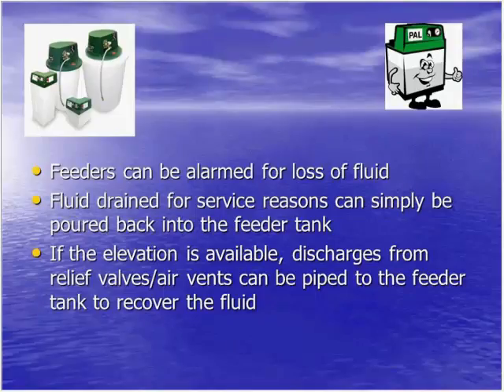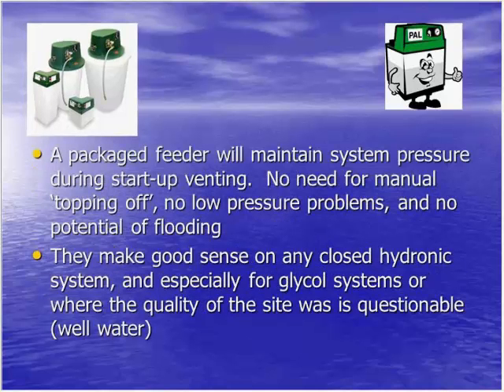Fluid that's drained for service reasons can simply be poured back into the tank. You can go change your control, whatever it may be, and then simply dump the fluid back into the reservoir. Also, if the elevation is available, discharges from relief valves and air vents can be piped to the feeder tank to recover that fluid as well. A package system feeder will maintain system pressure during startup venting, so there's no need for manual topping off, no low pressure problems, and no potential for flooding.